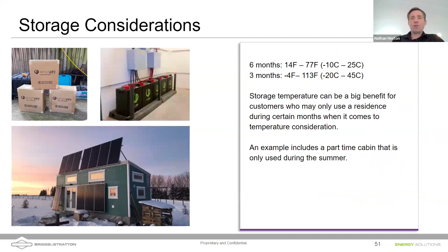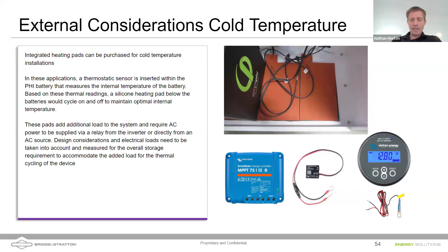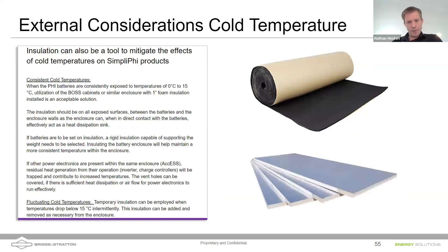I want to point out another great feature of our battery. One offering we have is heating equipment you can use in cold locations to heat the batteries up when they get too cold. We can integrate this directly into the BMS of our batteries, both our PHI and SimpliPHI batteries that go in these outdoor cabinets. We can put these heaters in and integrate them, and they turn on and off depending on the internal temperature of the battery. That's one option for cold weather.